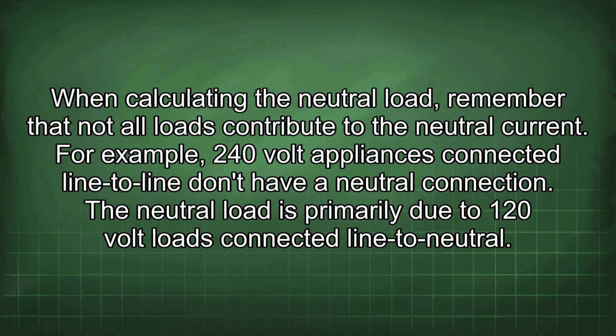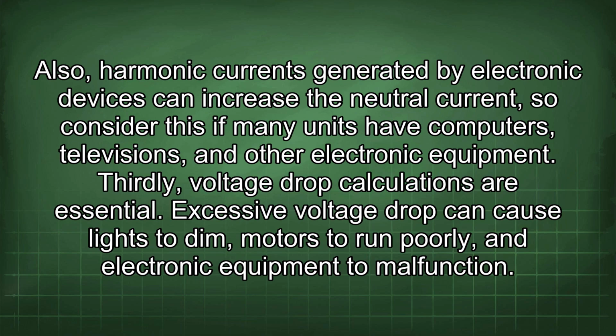When calculating the neutral load, remember that not all loads contribute to the neutral current. For example, 240 volt appliances connected line to line don't have a neutral connection. The neutral load is primarily due to 120 volt loads connected line to neutral. Also, harmonic currents generated by electronic devices can increase the neutral current, so consider this if many units have computers, televisions, and other electronic equipment.